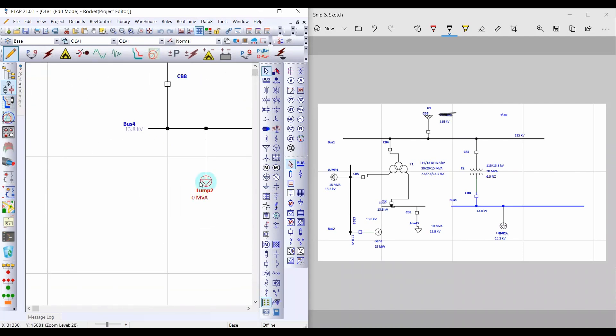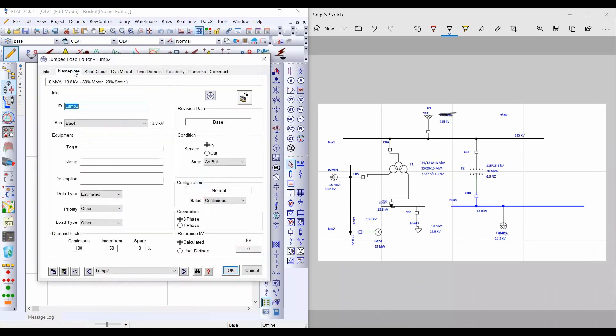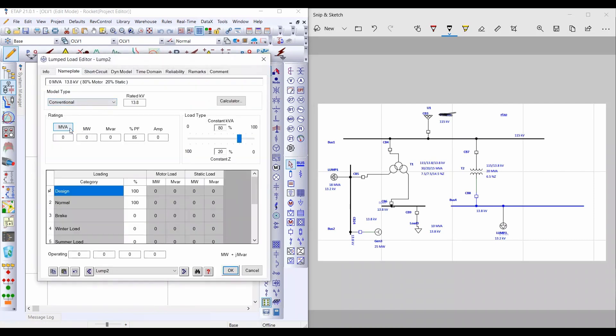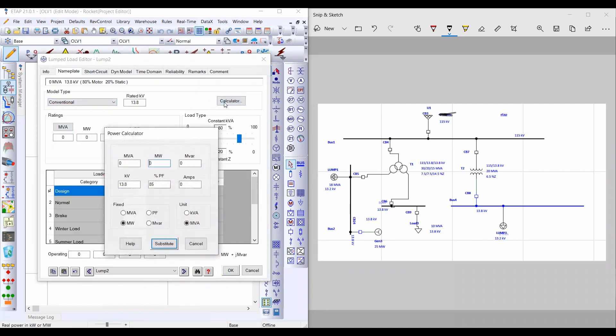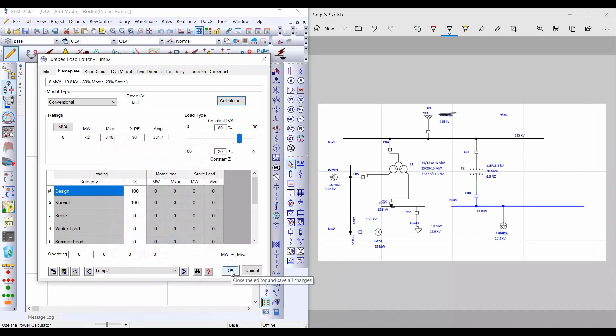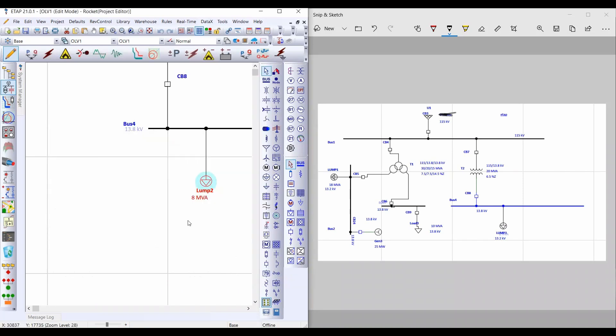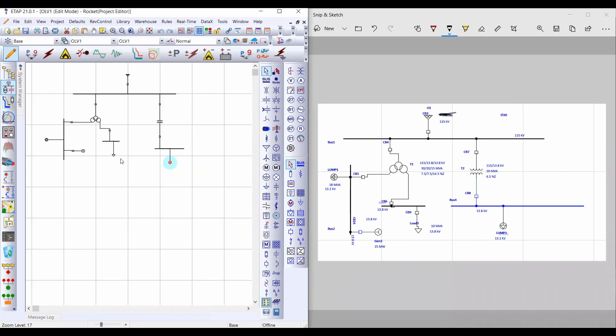Then double left-click on the first lumped load. From the Calculator, the value of this load is 8 MVA. Select Fixed MVA and insert 8 MVA, with a power factor of 0.90. Click Substitute.